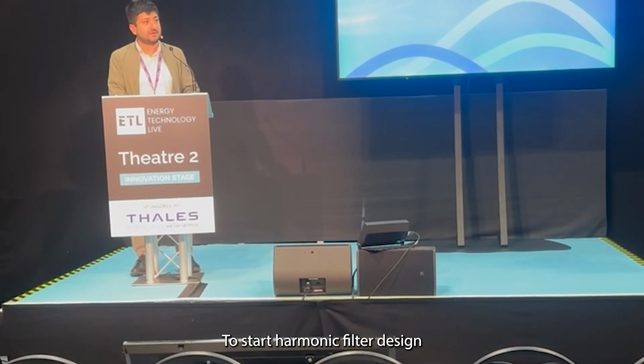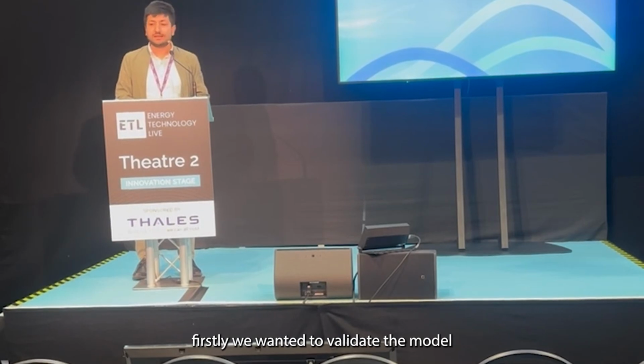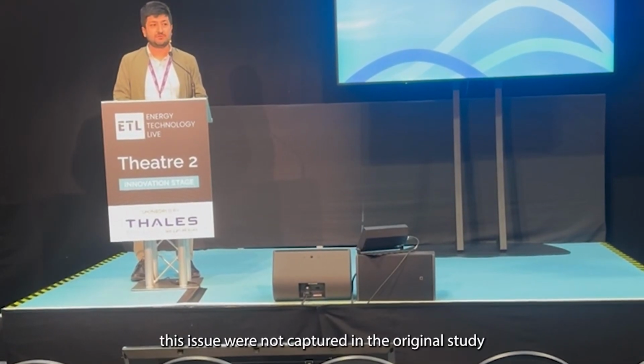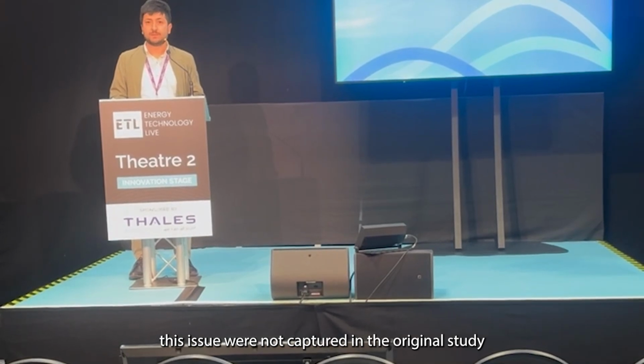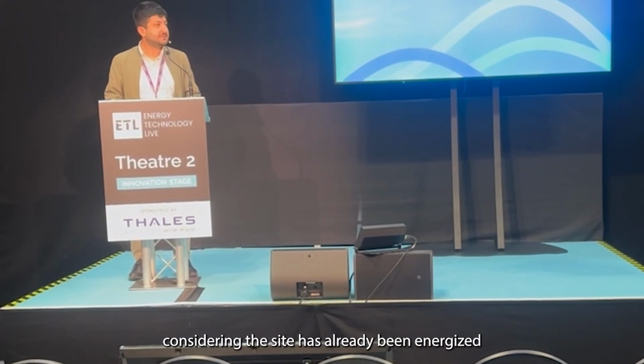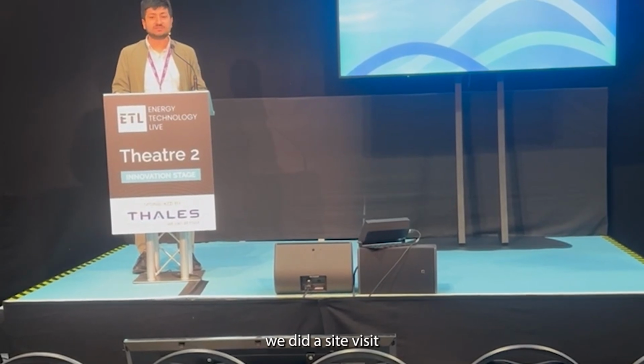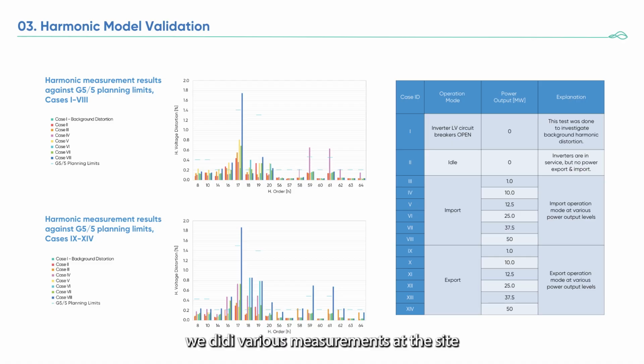Then, to start the harmonic filter design, firstly, we wanted to validate the model because these issues were not captured in the original study. So, considering the site had already been energized, we did a site visit and we did various measurements at the site. This is only a few of the measurements we have done. Basically, our measurements focused on different power output levels, not only maximum export and import power outputs. So from 0 megawatt to 50 megawatt, charging and discharging operation modes were analyzed in detail.